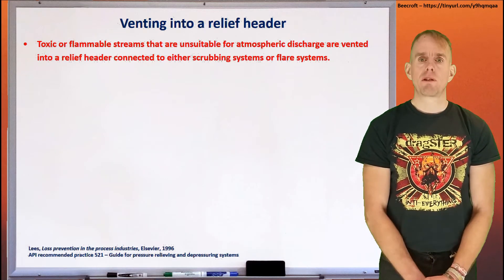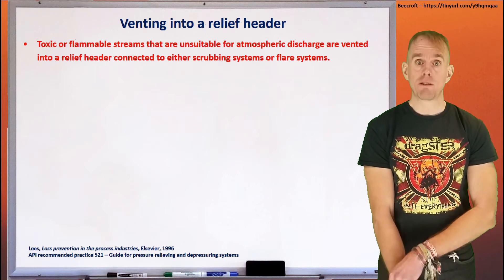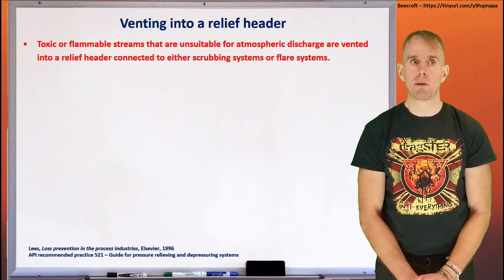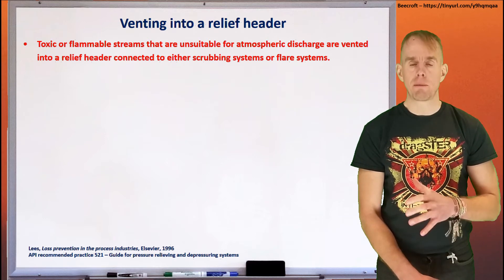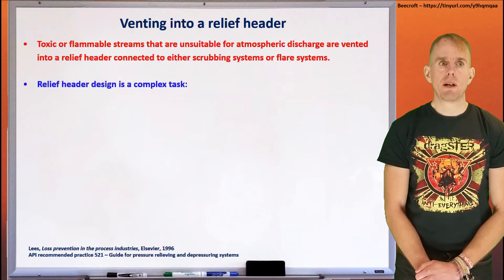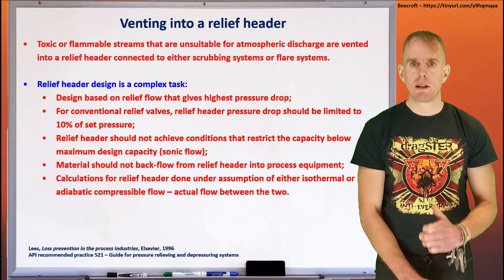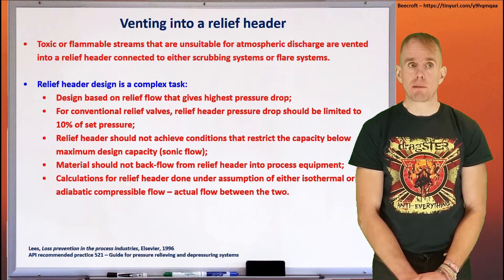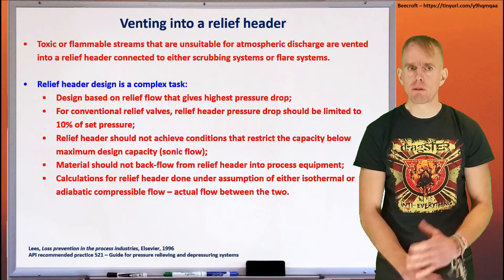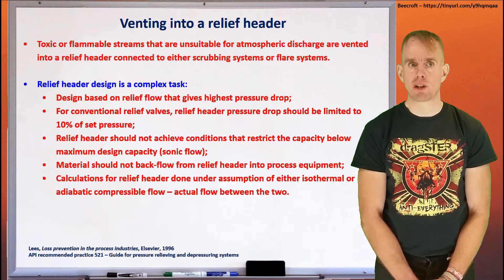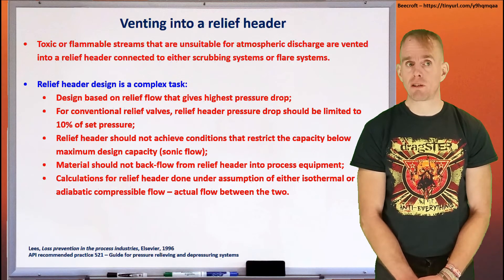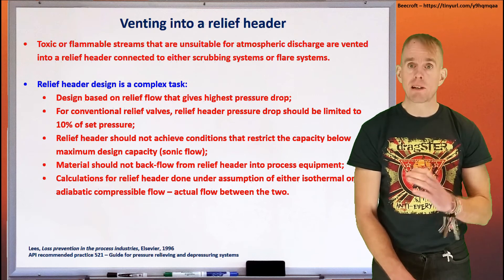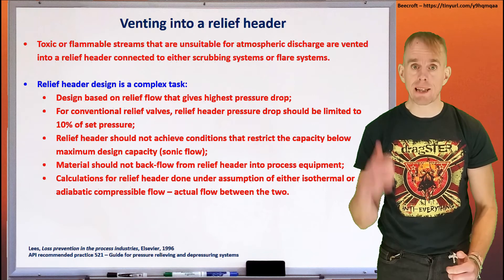If you can't dispose safely of a flammable or toxic gas through a relief valve, then you have to treat it somehow — discharging your relief device into a set of pipework. It's essential that this pipework doesn't put an upper limit on your relief system. So what we need to do is design a relief header, and we need to make sure it adheres to the following criteria: the design is based on the relief flow that gives the highest pressure drop — that might be a fire relief scenario from one or more vessels. For conventional relief valves, the relief header pressure drop should be limited to 10% of the set pressure of that valve. The relief header should never achieve conditions that restrict its capacity — for example, thinking back to compressible flow, even in a constant diameter piece of piping, a compressible gas will form a boundary layer that eventually will end up choking it under certain conditions, so that cannot happen in a relief header.